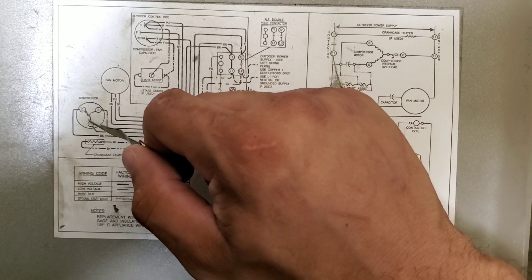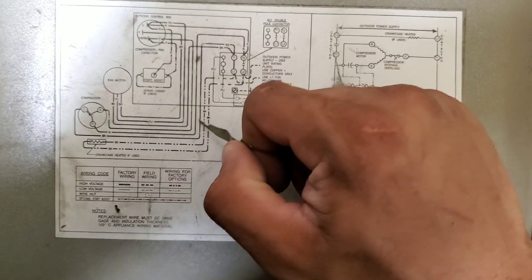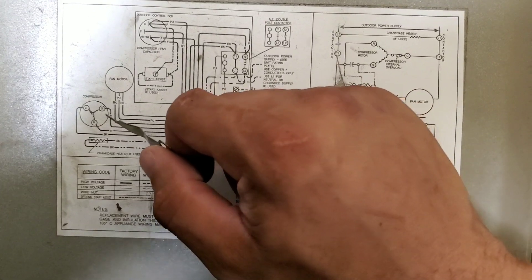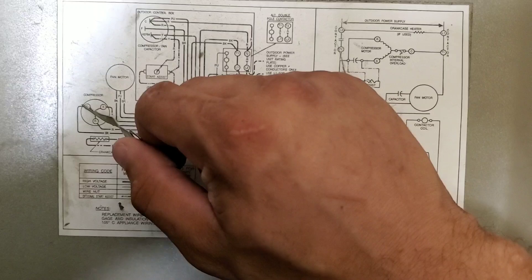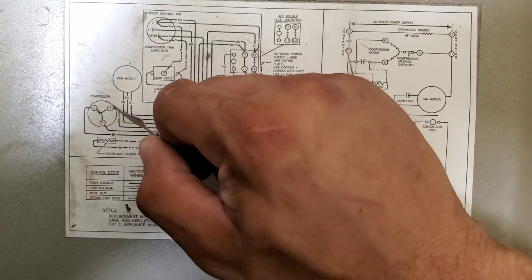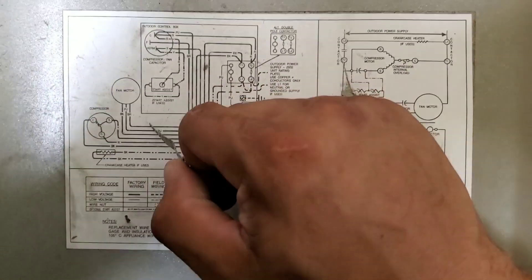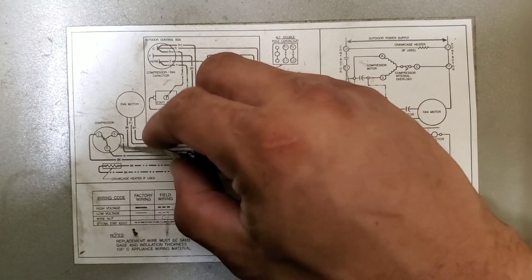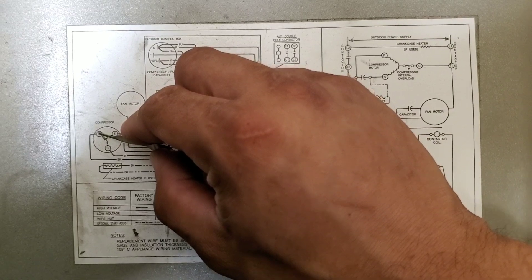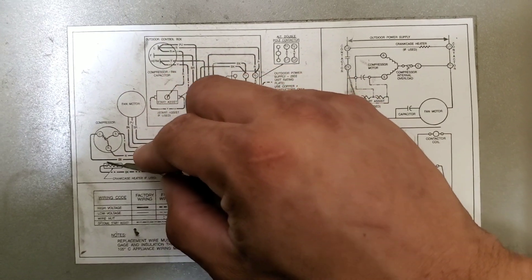What happens oftentimes, especially guys who are new to the industry, is they'll have a new compressor and they'll basically just cut the wires and try to tie them with wire nuts based off colors and not off what the schematic reads.